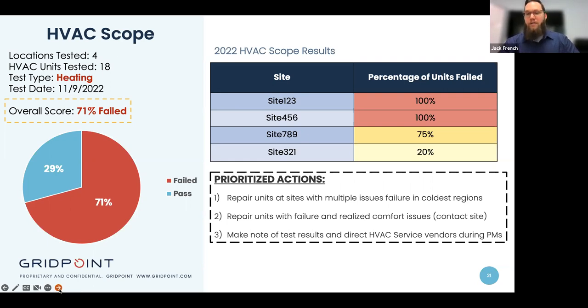So if you have a lot of sites spread out across a lot of different climate zones, maybe you are servicing sites up in Canada or up in the Northeast United States, those may be areas that you want to look at first because they're going to get cold first. And then kind of work your way down the list from there. Next, repair units with failure and realized comfort issues. So if you've had tickets opened by store managers or hot-cold calls from folks on site saying, hey, we've got an issue here, then you go to your scope results and see, oh, it looks like this unit actually failed the test.